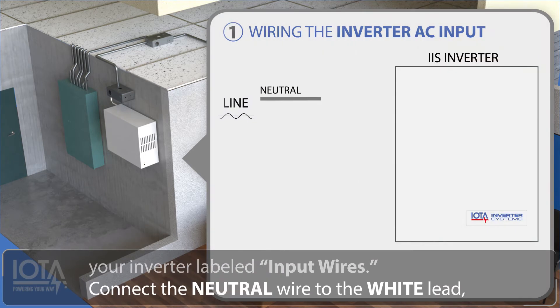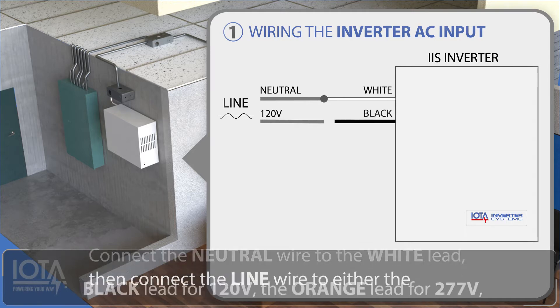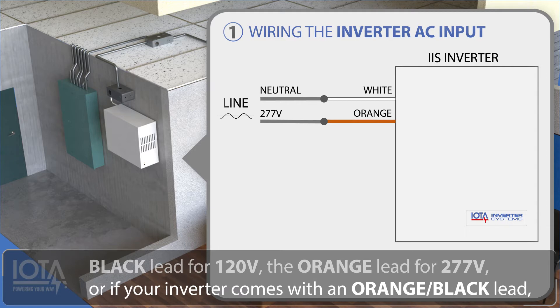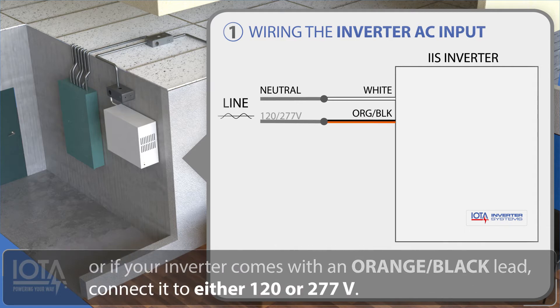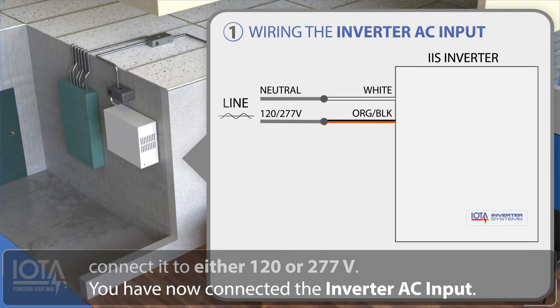This feed will be connected to the wires inside your inverter labeled input wires. Connect the neutral wire to the white lead. Then connect the line wire to either the black lead for 120 volts, the orange lead for 277 volts, or if your inverter comes with an orange-black lead, connect it to either 120 or 277 volts. You have now connected the inverter AC input.